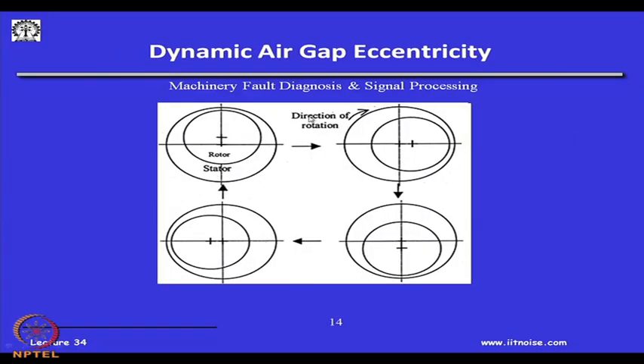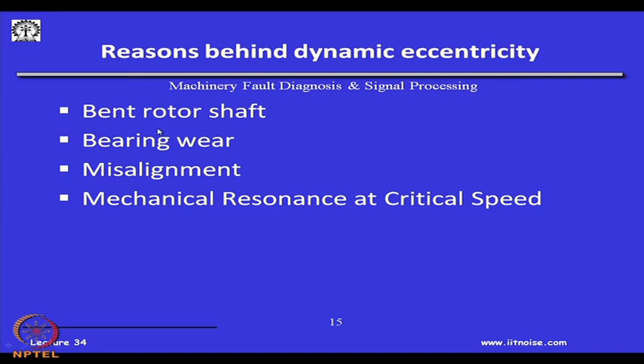And again, we will see frequency is coming up in this current spectra because of static eccentricity. Similarly, when it is rotating, I will have a dynamic air gap eccentricity. Okay. The eccentricity is moving with time. You can see how this thing is moving. This could be because the shaft is bent. Shaft is bent, so it is wobbling. Okay. So, one is the bent rotor shaft, other is the bearing wear, there could be misalignment, there could be mechanical resonance at critical speed, though a good motor designer would have ensured that the operating speed is not at its critical speed or much away from the critical speed. Okay. And once we have these kind of defects in the electrical motors, they all reflect in the current spectra.